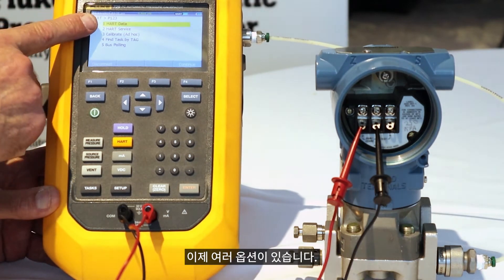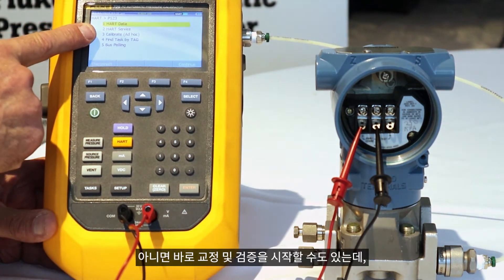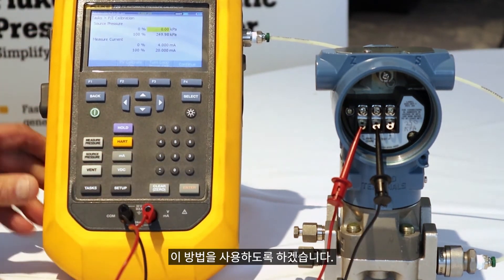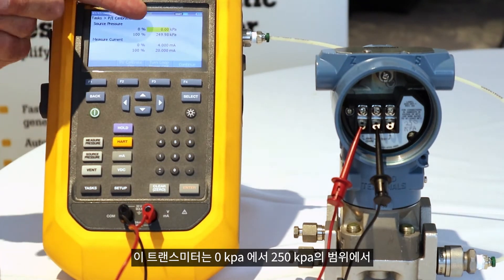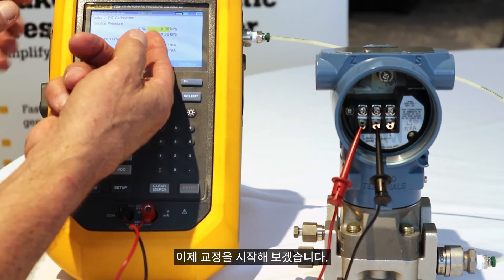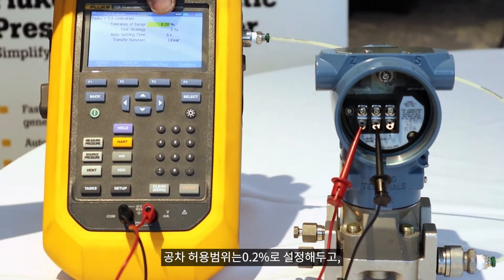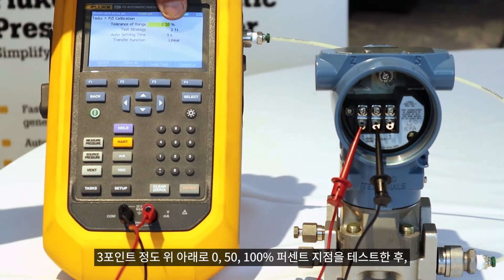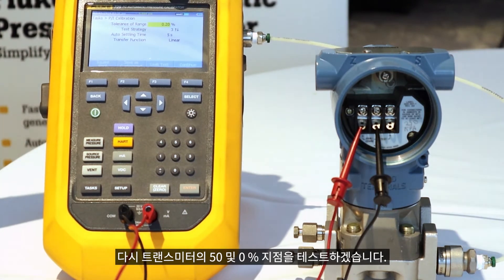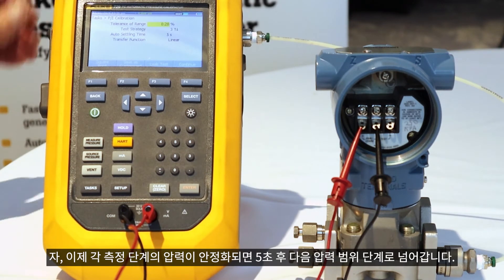So I have some options here. I can either look at the data, go in and do service trimming, etc., or I can do a calibration — an ad-hoc calibration, which I'll do now. I've identified that this device is 0 to 250 kPa and will measure 4 to 20 milliamps. We're going to test the 0.2% tolerance. We're going to do a three-point up-down test: 0, 50, 100%, and then 50 and 0% of the range of the transmitter. The calibrator is going to settle for five seconds on each measurement step.